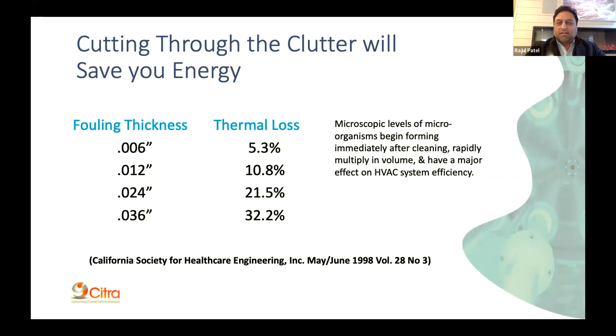Now getting to the energy savings part of UV, how does this work? How does this blue light in the HVAC system save energy? Here's a study done in 1998 by the California Society of Healthcare Engineering. They looked at different levels of fouling on a cooling coil and the associated thermal losses. The fouling, otherwise known as a biofilm, ranges from 6 thousandths of an inch to 36 thousandths of an inch. At 36 thousandths of an inch, you're losing 32% thermal loss. These are things happening in every air handler and rooftop unit, and adjustments are being made by facilities that compensate for this over time, but it's increasing energy usage.